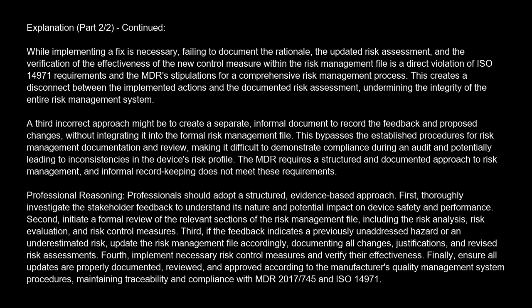A third incorrect approach might be to create a separate, informal document to record the feedback and propose changes, without integrating it into the formal risk management file. This bypasses the established procedures for risk management documentation and review, making it difficult to demonstrate compliance during an audit, and potentially leading to inconsistencies in the device's risk profile. The MDR requires a structured and documented approach to risk management, and informal record-keeping does not meet these requirements.